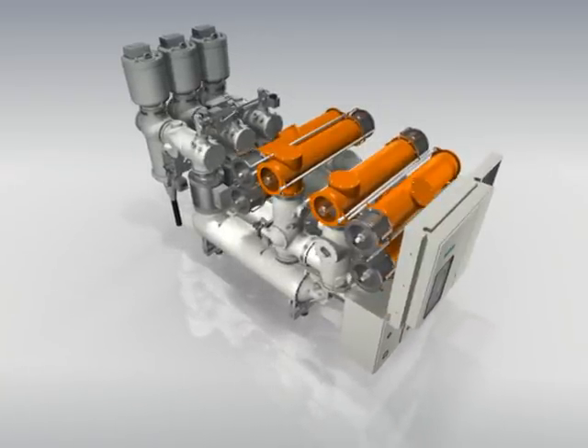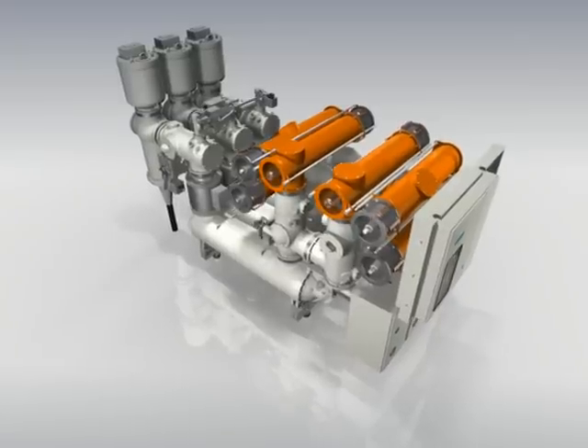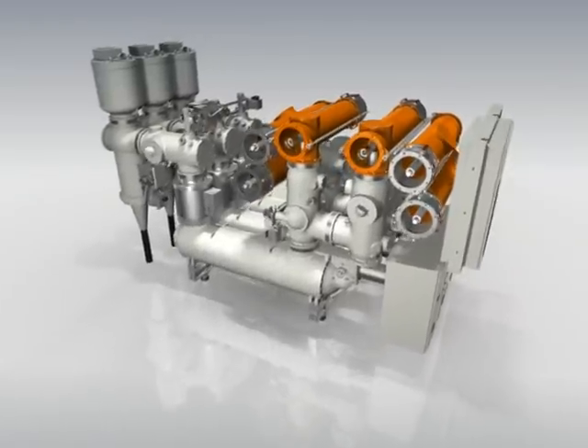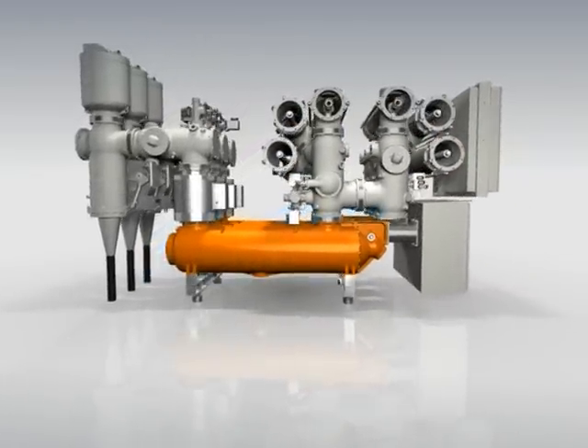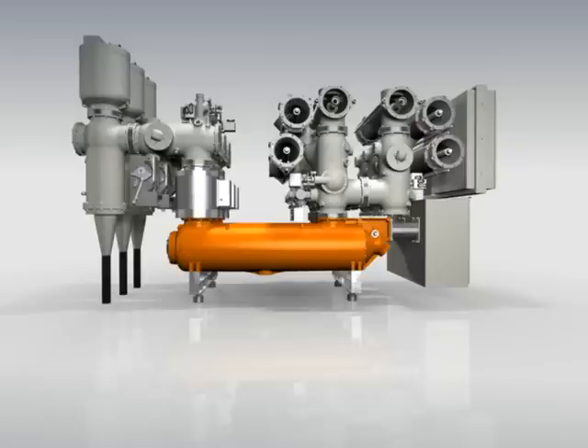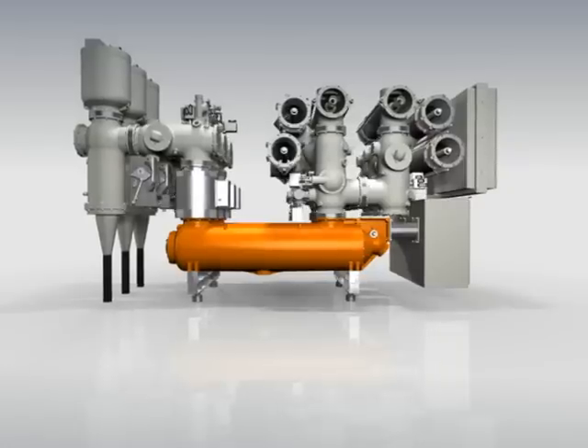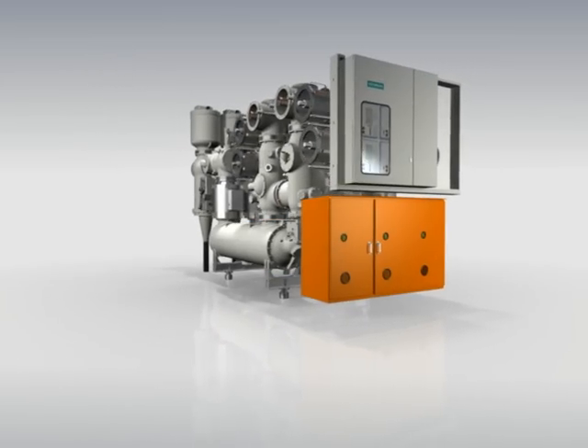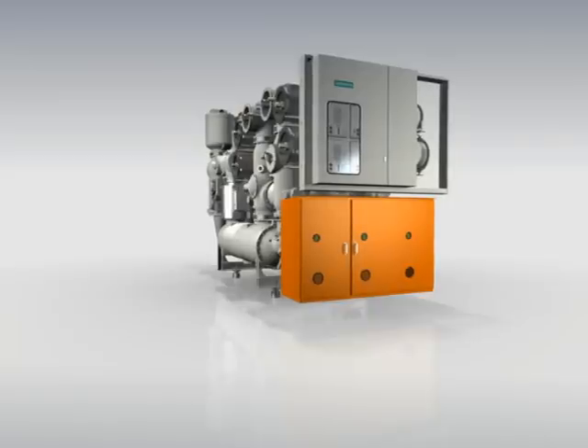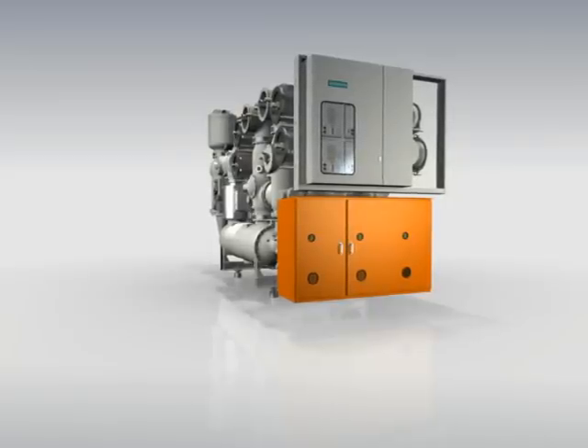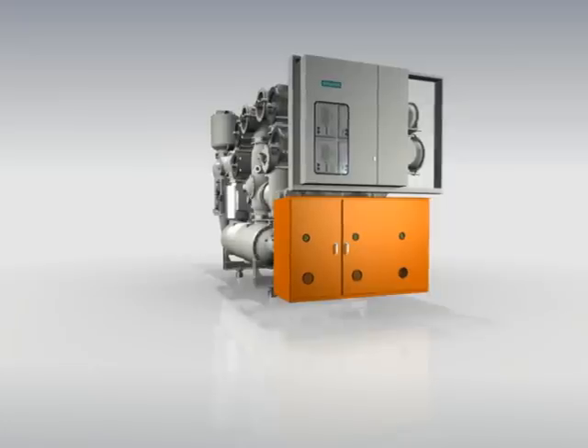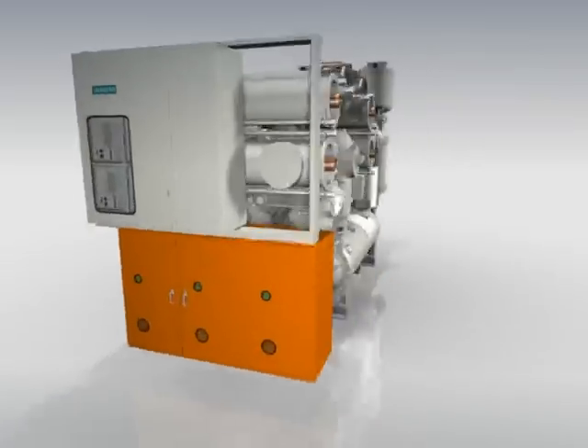Passive busbar modules without any electrical and mechanical activity guarantee reliable operation and make busbar failures more than unlikely throughout the entire lifetime of the switchgear. Furthermore, during extension or maintenance works, at least one busbar remains in service. The circuit breaker module, which contains the interrupter unit, is the central element of the gas-insulated switchgear. The spring-stored energy mechanism provides the force for opening and closing the circuit breaker for a short-circuit breaking current of 63 kA within only 2 cycles.